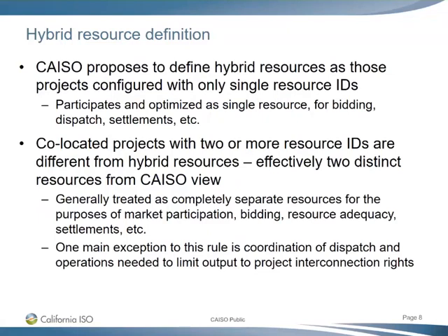Hybrid resources will essentially be those single resource ID combinations, participating as a single resource optimized by the resource owner or scheduling coordinator — treated as a single resource for bidding, participation, dispatch, and settlements. Co-located projects are still addressed through this initiative because they include combinations of different resources, but we're differentiating those and calling them co-located projects. Those have two or more resource IDs at a single point of interconnection, are treated as completely separate for market participation, bidding, RA, and settlement. The main exception is that they could have a coordinated dispatch limited to their total overall interconnection rights.